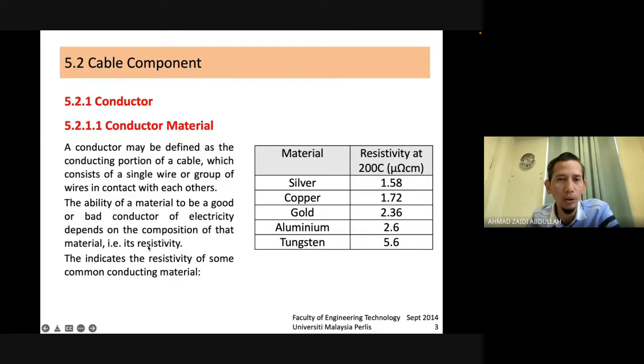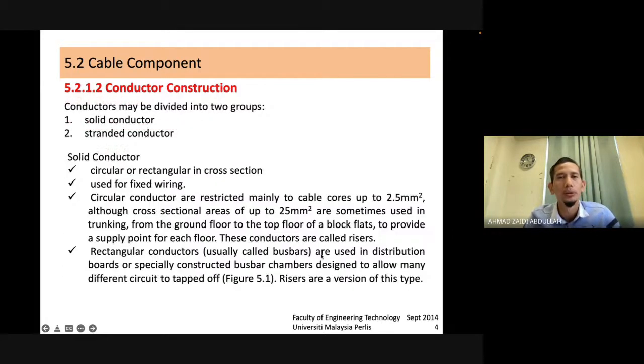The ability of a material to be a good or bad electrical conductor depends on its composition, the resistivity. This value of resistivity is reflected in the selection of the material. Conductors may be divided into two groups, solid conductor and stranded conductor. A solid conductor, which is circular or rectangular in cross section, is used for fixed wiring. Circular conductors are restricted mainly to cable cores up to 2.5 mm. It is only one solid core, not combined with any strands. Stranded, as I mentioned earlier, has 3, 5, 7 and so on.